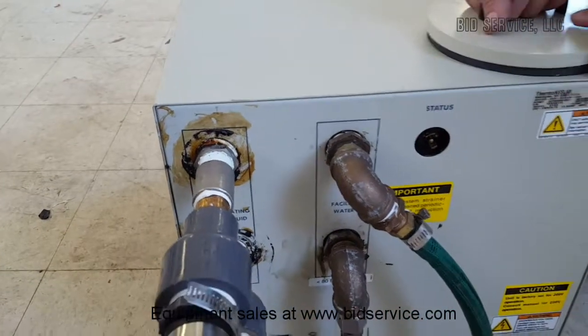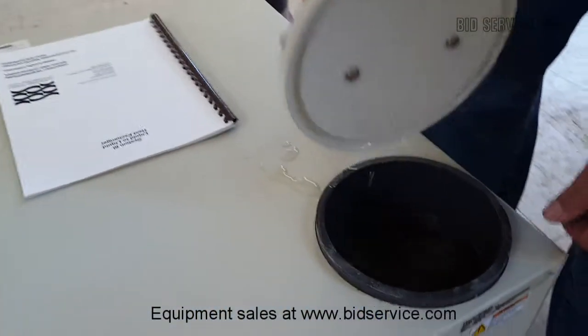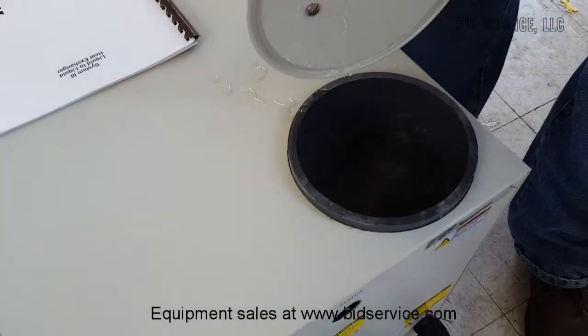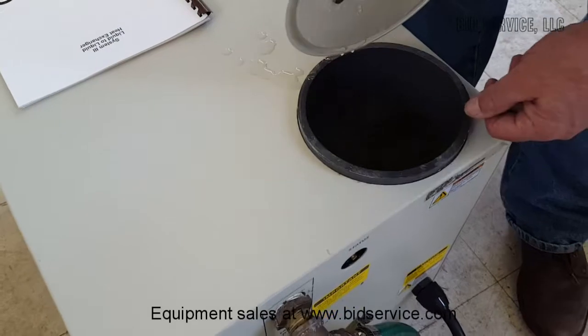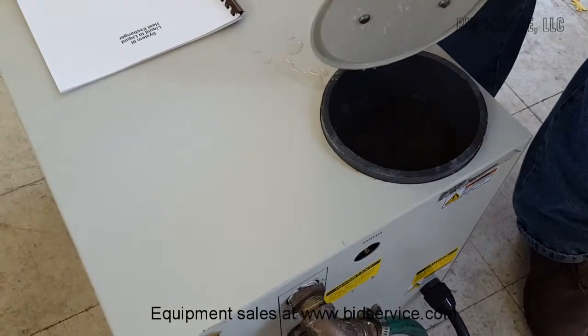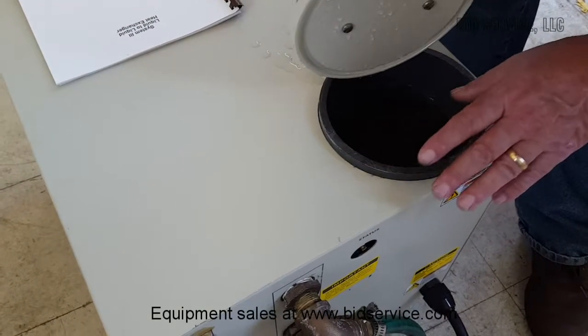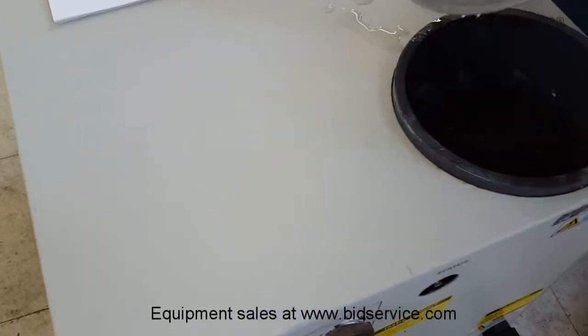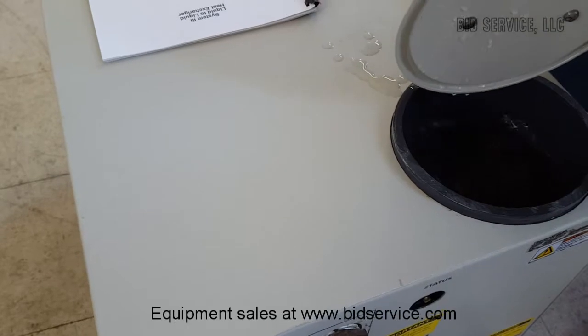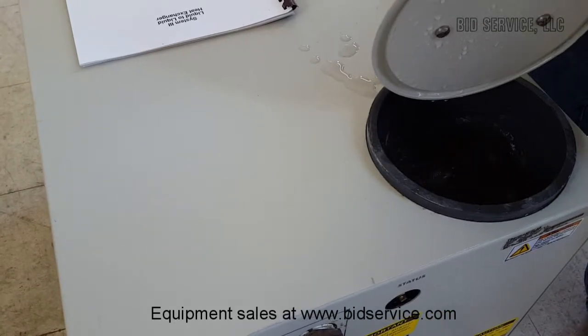And when you're filling this up for the first time, there's a reservoir, and that reservoir is here. And as you can see, we're pumping fluid through here, and this is what's going through the load. So you want to make sure, and it explains this in the manual also, that you need this level high enough. There's a float switch in here, and if it's too low, it will error out, and then you have to reset it.